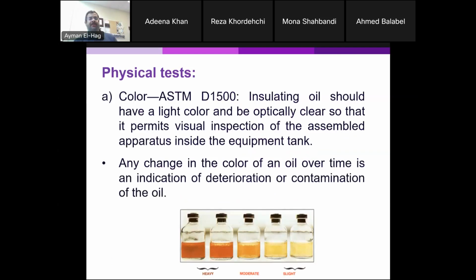This is the easiest test, the simplest test, but it is very, very effective. So this is done as per ASTM D1500. You need just to take a sample from the oil, and usually we can take it from the oil drainage valve. Usually you have one at the bottom of the transformer tank. So you take the sample in some sort of transparent container so you can see inside it and see the color. Now, when you look here at the color of the transformer oil, this is good. Okay, as we go this way, it's getting worse and worse. And you see here clearly that the color starts to get darker and darker.